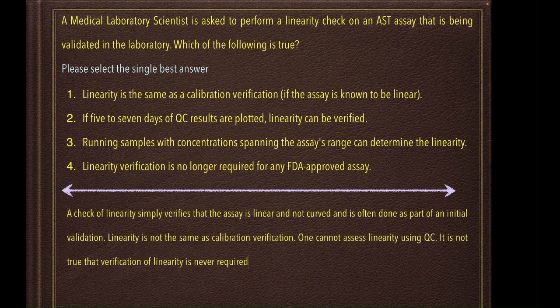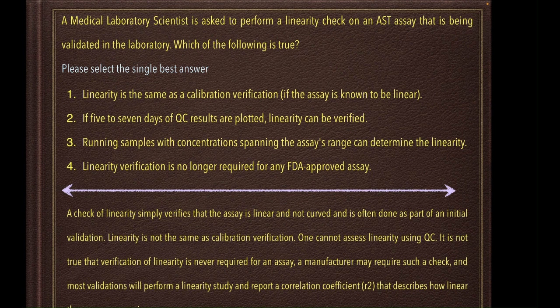The answer. A check of linearity simply verifies that the assay is linear and not curved, and is often done as part of an initial validation. Linearity is not the same as calibration verification. One cannot assess linearity using QC. It is not true that verification of linearity is never required for an assay. A manufacturer may require such a check, and most validations will perform a linearity study and report a correlation coefficient, R2, that describes how linear the assay response is.